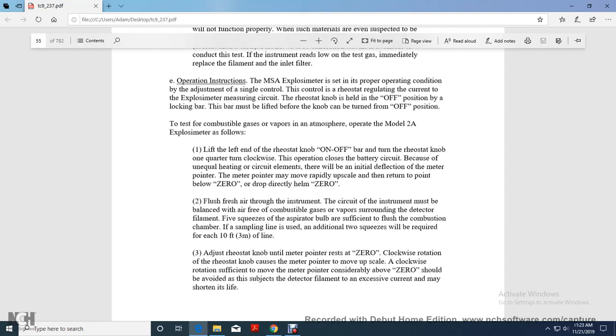Operate the Model 2A explosimeter as follows. Lift the left end of the rheostat knob's on-off bar and turn the rheostat knob a 1/4 turn clockwise. This closes the battery circuit. Because of the unequal heating of the circuit elements, this will initially result in deflection of the meter pointer.